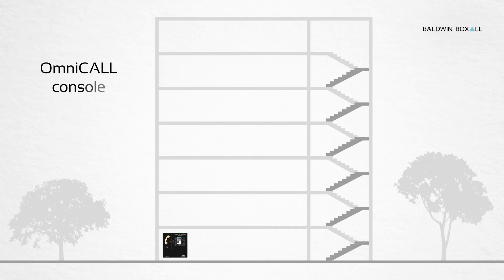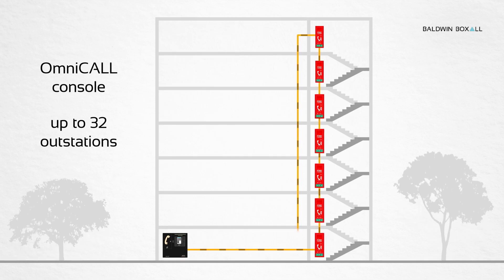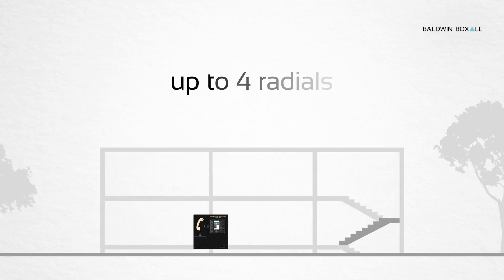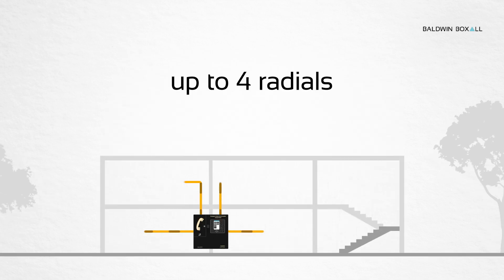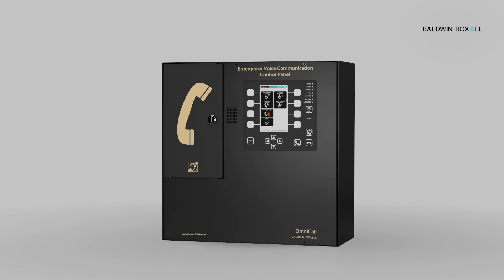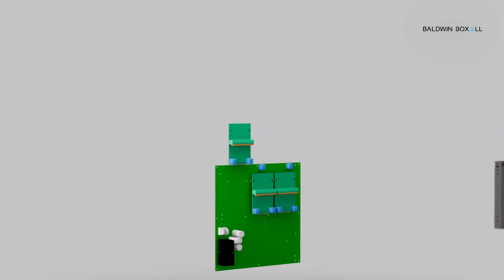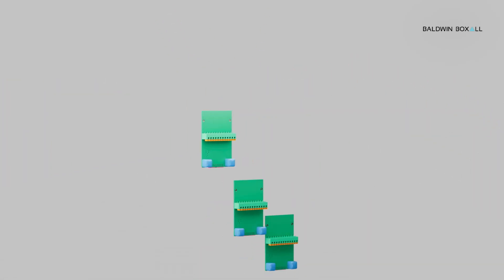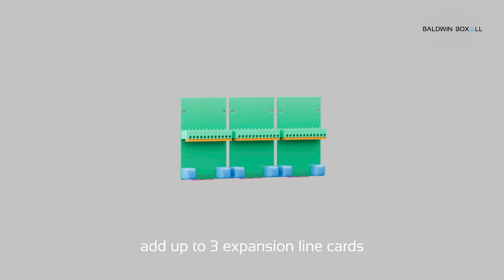The OmniCall console supports 32 outstations on a loop or up to four radials using two core cables for loops or radials. Add up to three expansion line cards for 16 radials or four loops in any combination.